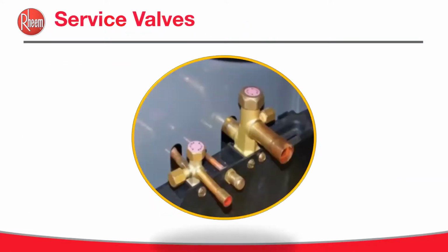So now let's look at the service valves, the connection point for liquid and suction lines. After you remove the cap, the liquid line needs a 3/16 Allen wrench to open the valve. The big thing is to make sure you have the proper wrench. Some people are using sockets and they're not long enough, so you can end up stripping the valve. So make sure you have the proper Allen wrench, deep enough to reach the bottom of the valve itself.